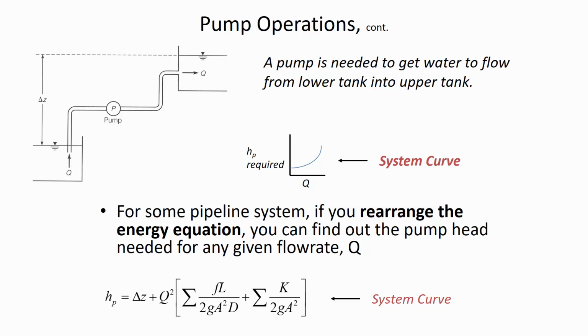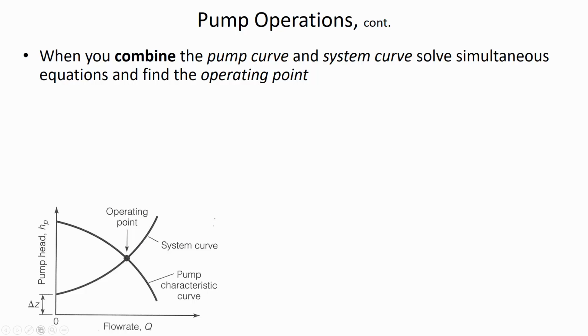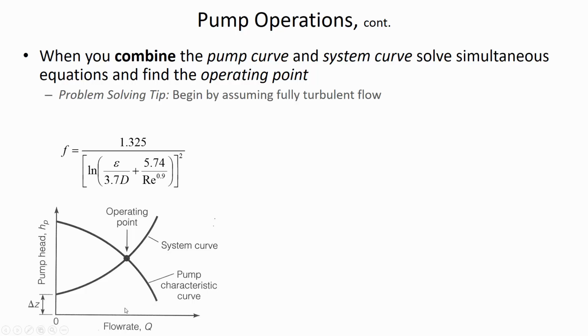So if you set the system curve equal to the pump curve and solve for Q, then you'll find that operating point. It's really easy to solve problems like this. You just combine the pump curve and the system curve together, and then it'll tell you what flow rate you're getting. Now, the challenge is that in the energy equation, you're supposed to have a friction factor F.